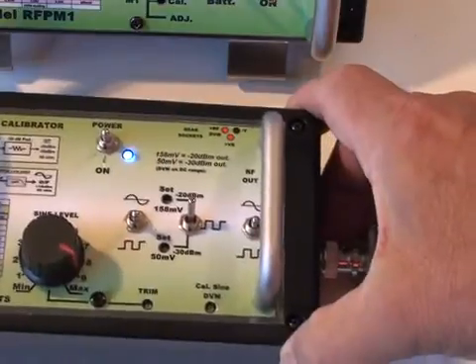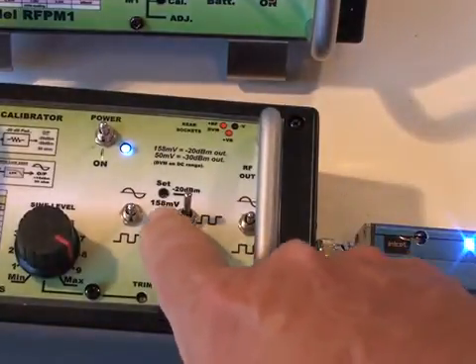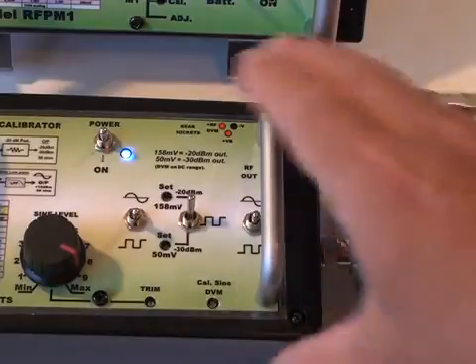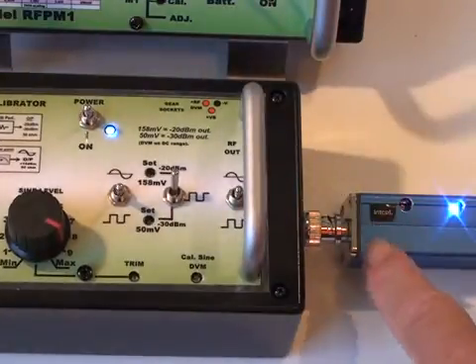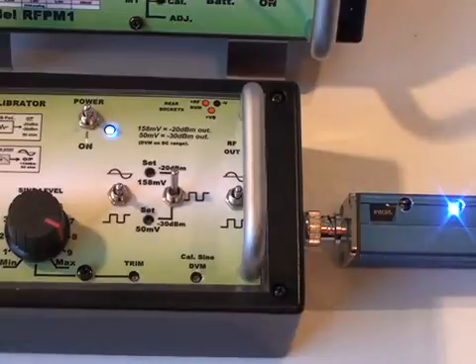And you can then adjust the two levels using the trim pots so that you get a fairly precise minus 20 dBm and minus 30 dBm signal into the RF power meter. And that way you can calibrate the power meter.